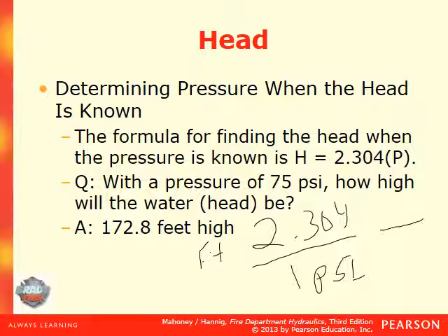They gave us 75 psi as the head pressure. So 2.304 times 75 divided by 1 gives us our answer of 172.8 feet high.